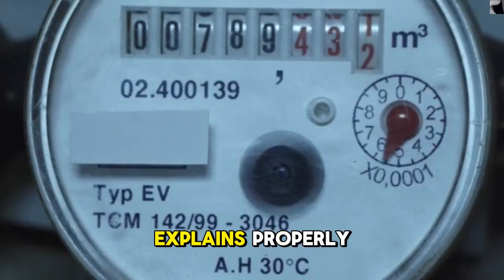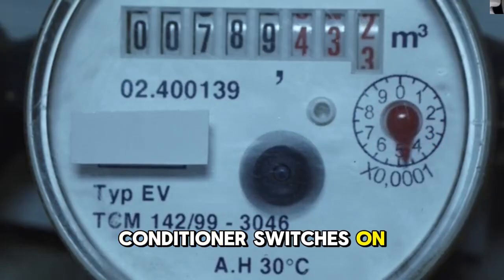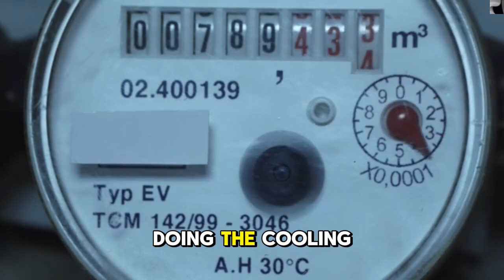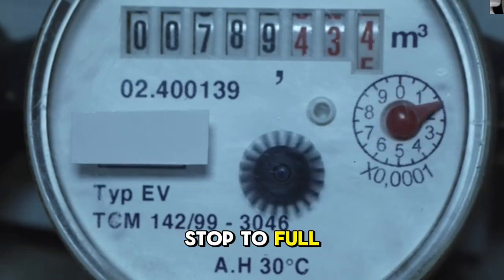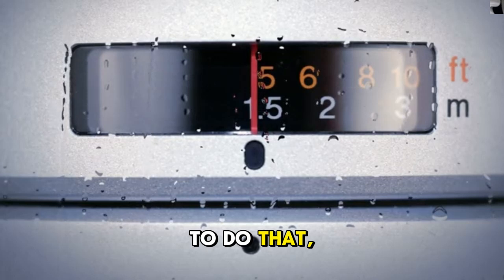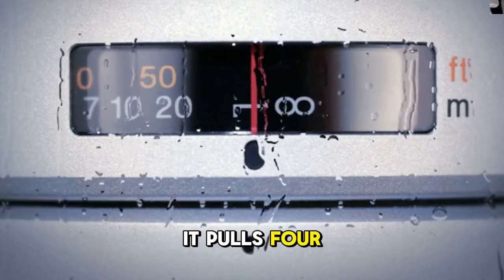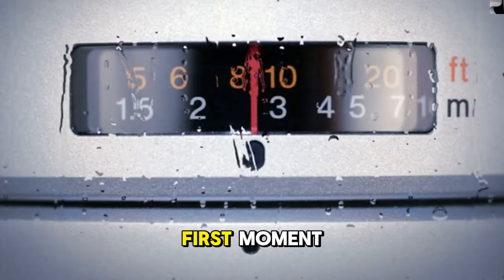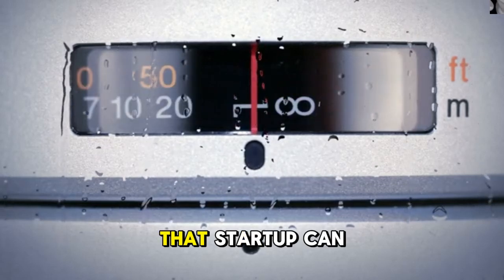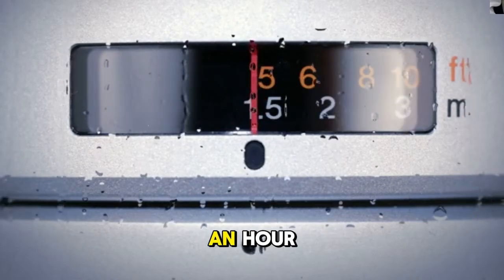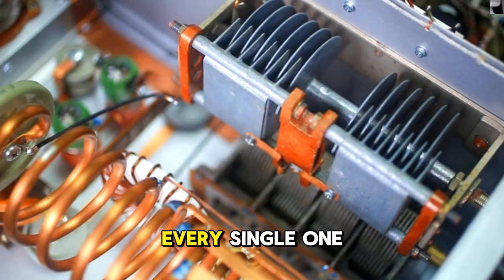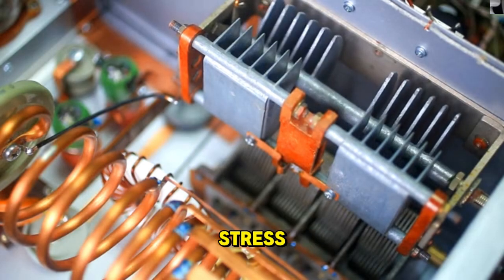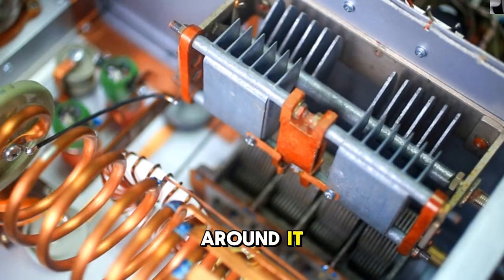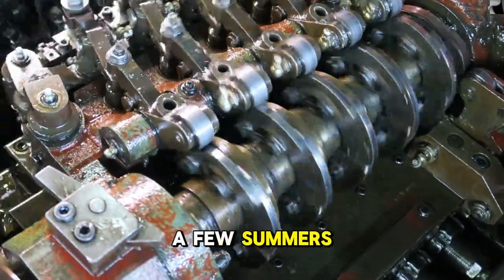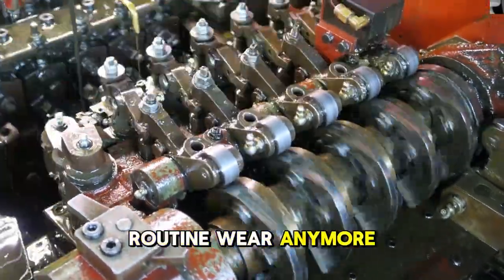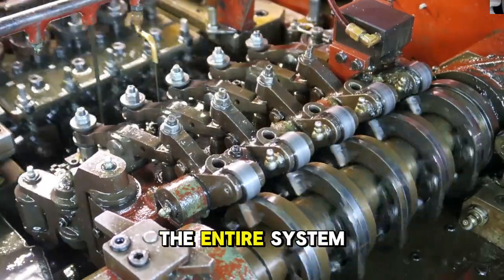Here's the problem nobody explains properly. Every time your air conditioner switches on, the compressor, the part actually doing the cooling, has to jump from a dead stop to full speed in a couple of seconds. To do that, it doesn't just draw a little extra power. It pulls 4 to 8 times its normal running current just for that first moment. On a hot day, that startup can happen 6, 7, 8 times an hour. Every single one of those moments puts a jolt of heat and stress through the compressor and the wiring around it. Do that thousands of times over a few summers, and you're not looking at routine wear anymore. You're looking at the most expensive failure in the entire system.